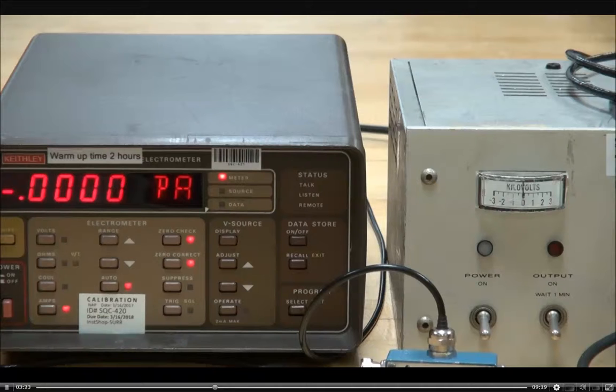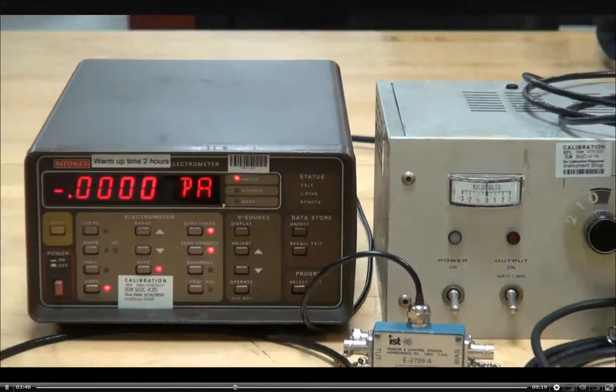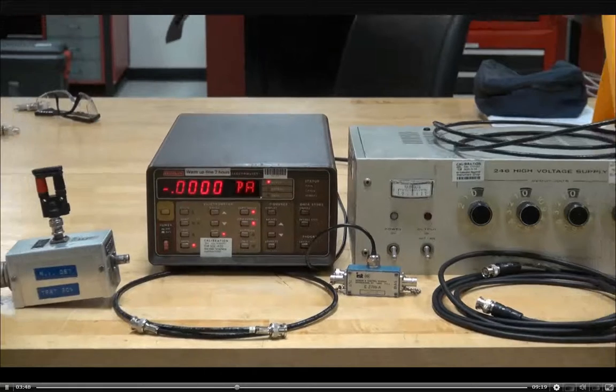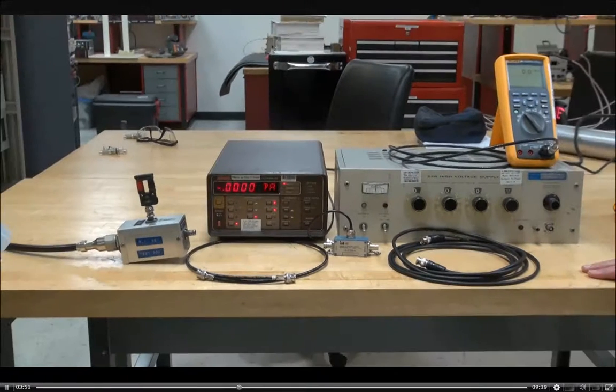Okay, there's some warnings. Extreme care should be used when working on or in close proximity to energized equipment. Energized equipment may produce a shock. In the setup on attachment 2, the electrometer will float above ground in the potential of the applied voltage. The connector on the coaxial adapter box and cable will also be at power supply potential. To avoid shock, insulated tools such as fuse pullers or insulated screwdrivers should be used when operating the electrometer while the power supply output is on.